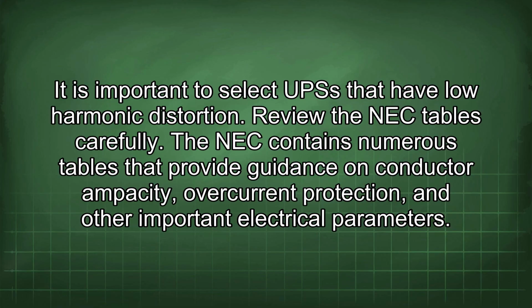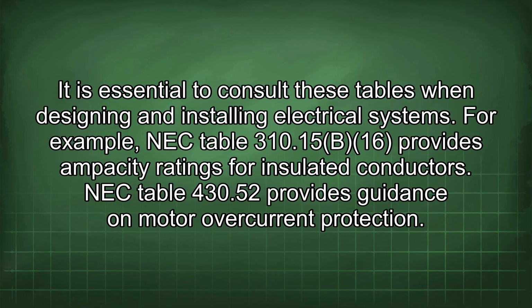Review the NEC tables carefully. The NEC contains numerous tables that provide guidance on conductor ampacity, overcurrent protection, and other important electrical parameters. It is essential to consult these tables when designing and installing electrical systems. For example, NEC Table 310.15(B)(16) provides ampacity ratings for insulated conductors. NEC Table 430.52 provides guidance on motor overcurrent protection.